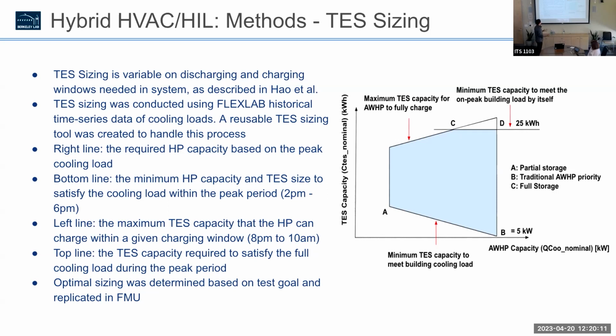I'll try to breeze through this a little bit, but business as usual with no thermal energy storage is this point B here, which is you size your system to meet that peak load. But with thermal energy storage, you could theoretically downsize your system all the way to point A, where you still can provide the same amount of service, but now you have a certain amount of TES capacity that could help with that lacking capacity.